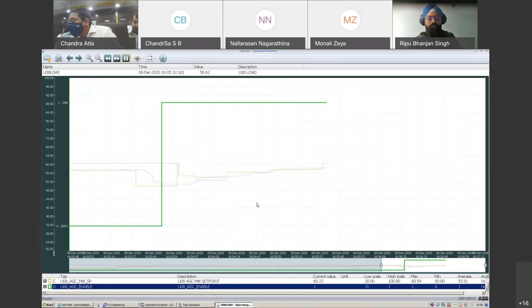Yeah, you can see on the right hand side, the instant values will come. People can zoom it if it allows, because this can make things clearer. So now you can see this AGC signal is on for this particular unit at a particular time. You can zoom this part. See, now the signal status has been changed. Once the signal status is changed, you can highlight the AGC signal from the SLDC. This colored one is the AGC signal which is coming from the state load dispatch center.